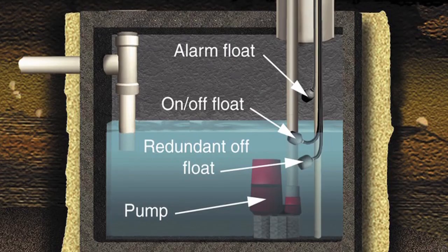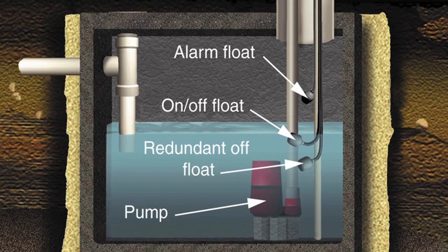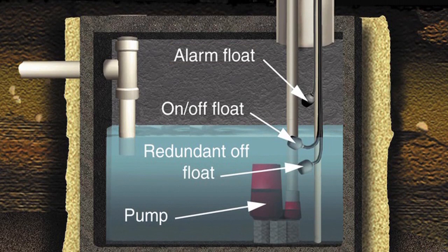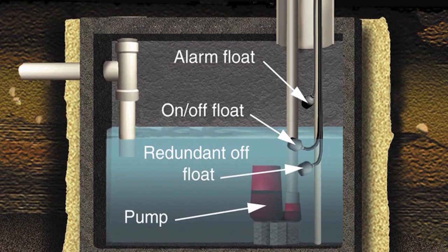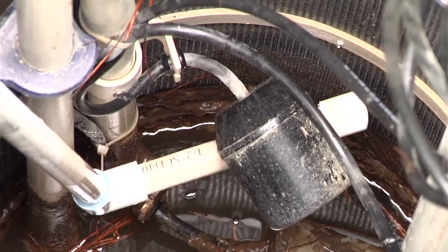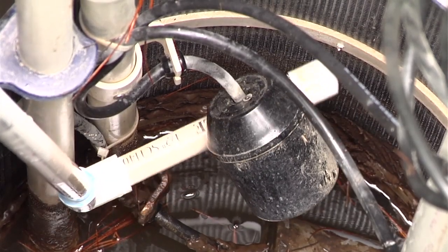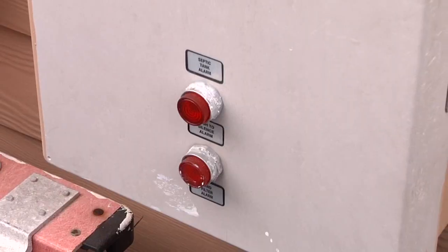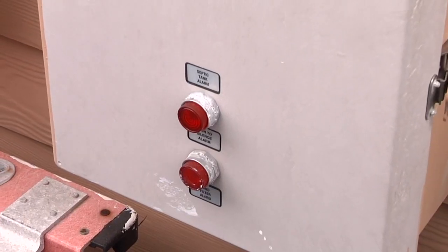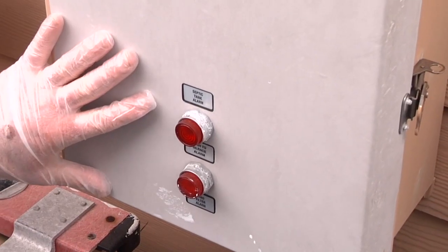The third and highest float is the alarm float. If the pump fails or too much wastewater enters the pump tank, the wastewater level rises and lifts the alarm float, which sounds an alarm on the control panel near the house. Push to silence it and then call a licensed professional. The alarm is there to let you know there's a problem, so don't ignore it.